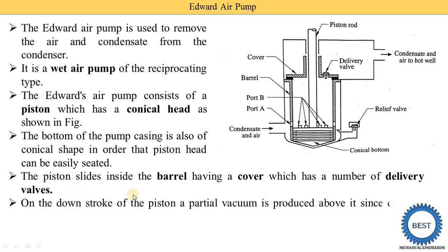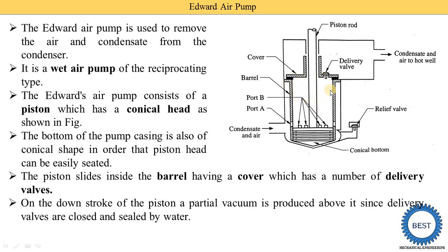On the downstroke of the piston, a partial vacuum is produced. When the piston starts to move in the downward direction, a vacuum is created inside the barrel. When this vacuum is created, the delivery valve is closed, and it is sealed by the water — the condensate and water present there covers the delivery valve.